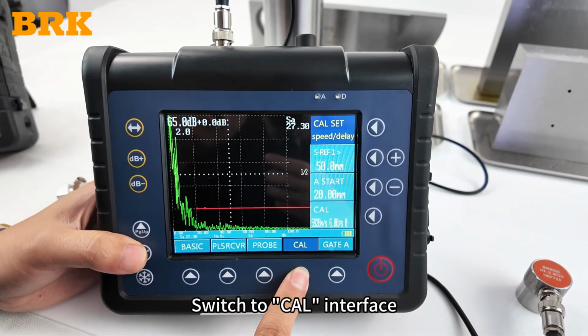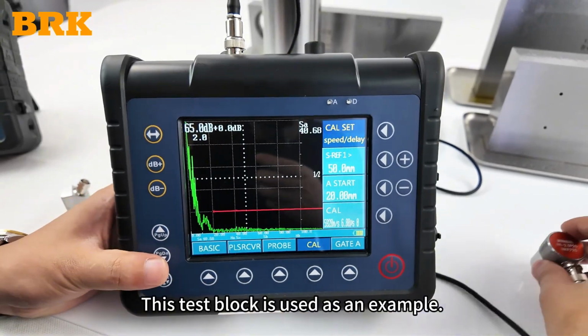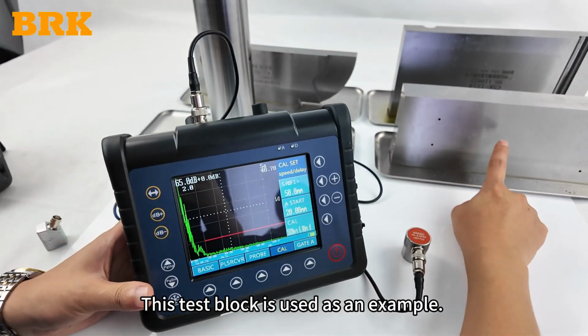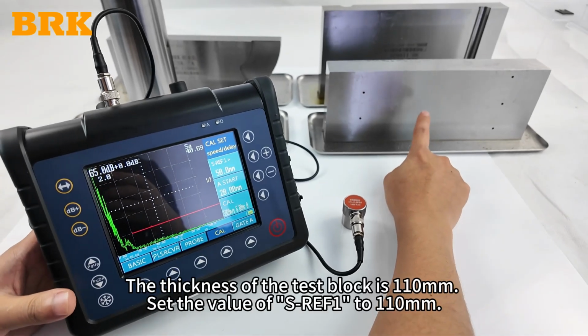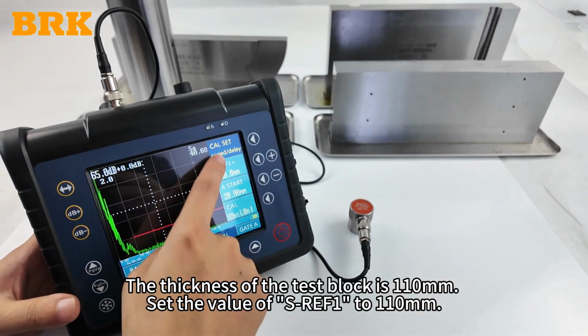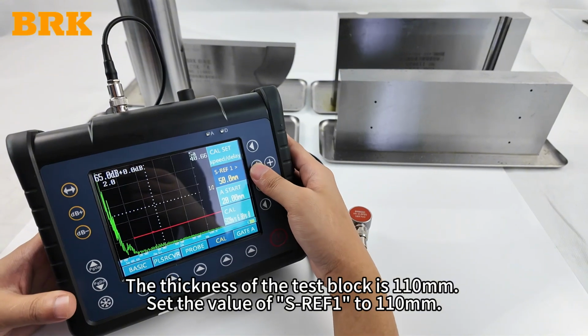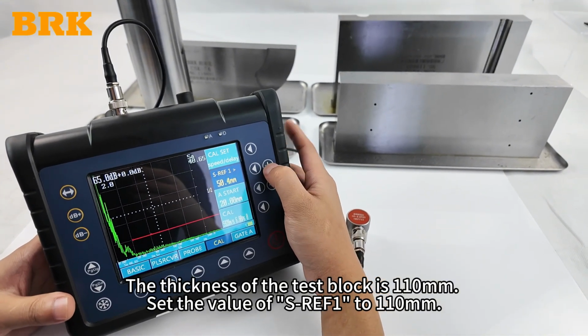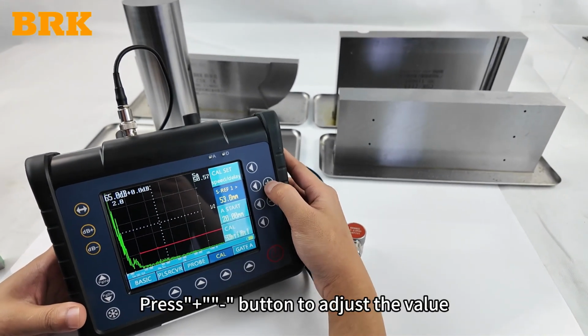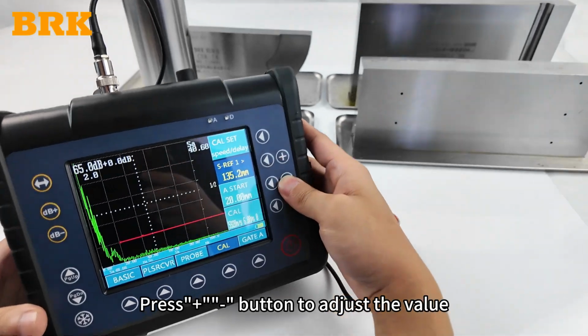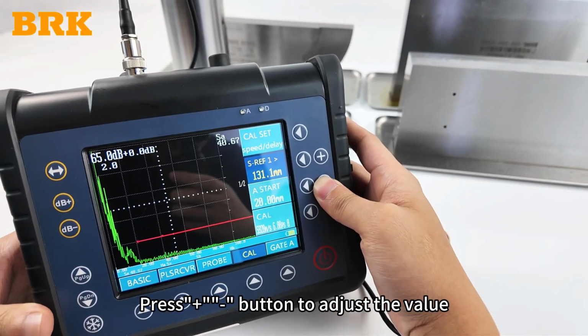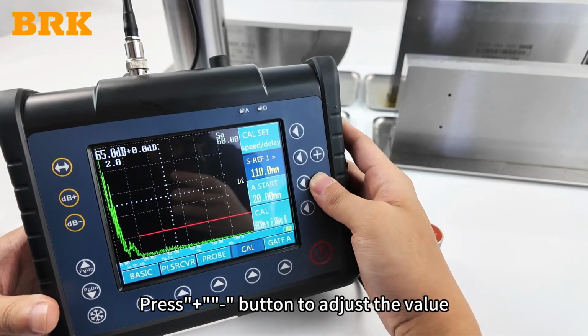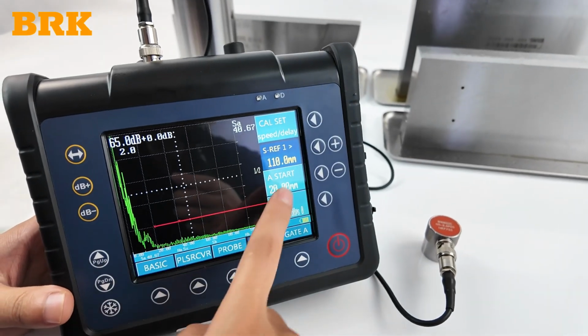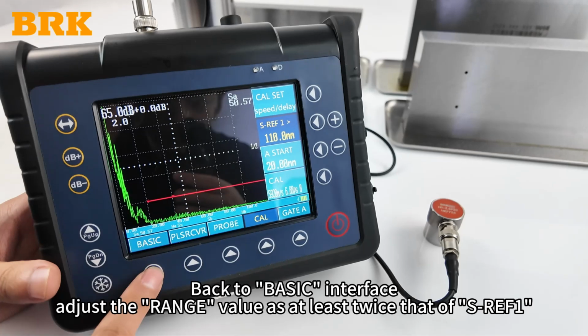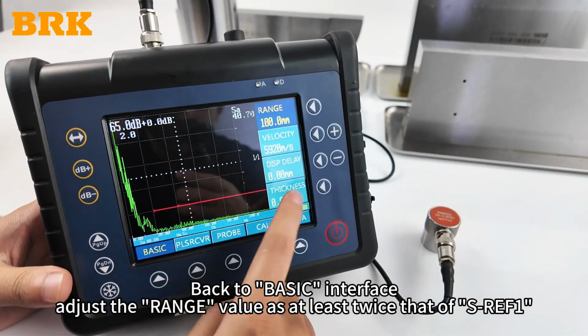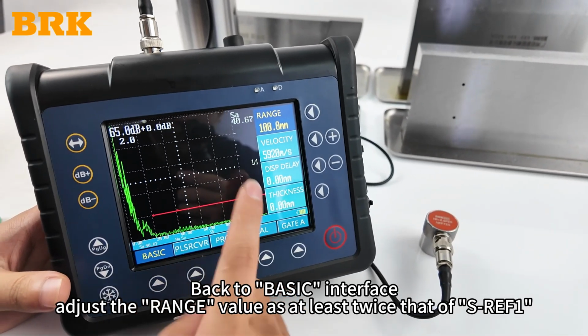Switch to Cal interface. This test block is used as an example. The thickness of the test block is 110 millimeters. Set the value of S-REF1 to 110 millimeters. Press plus button to adjust the value. Back to basic interface, adjust the range value as at least twice that of S-REF1.